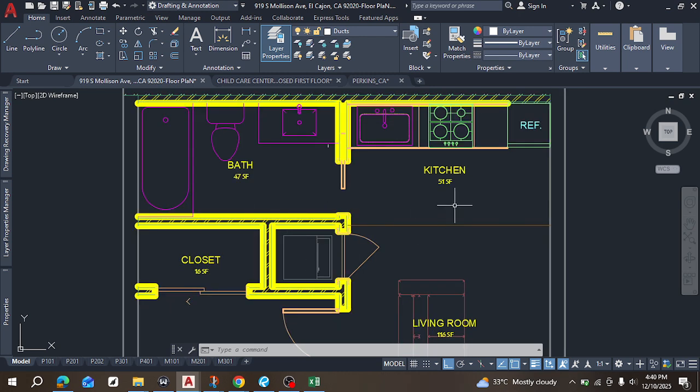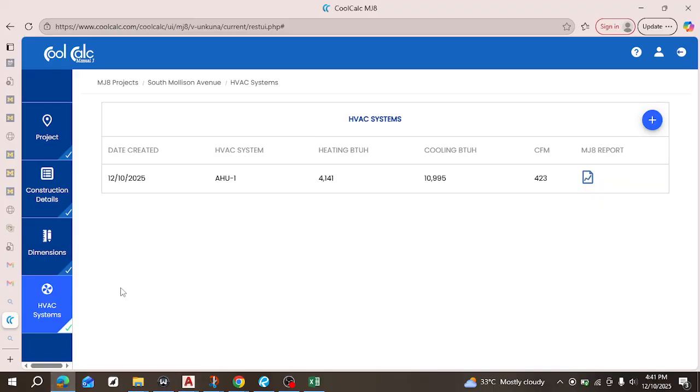300. And now, normally we would have multiplied by 0.8, and that would have given us 300 times 0.8, that is 240. Now, because of spaces like the kitchen, I would have raised it up to like 300, 400. So you see that the rule of thumb is sometimes close, but not in all cases, right? Not in all cases.